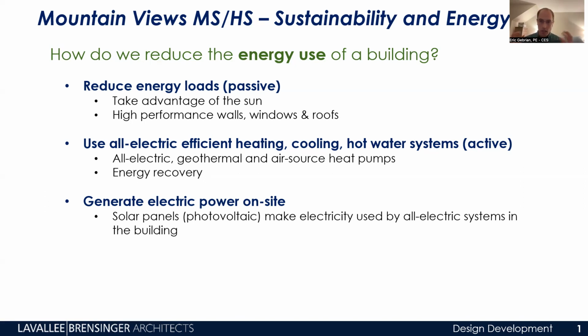We heat all that incoming air to 70 degrees in the wintertime—if we just exhausted it with no energy recovery, that would be a huge waste of energy, kind of like going right out the chimney. So we have energy recovery on our ventilation equipment that keeps about 70 to 80% of that energy back in the building. Those are the two major HVAC technologies we're using to really lower our energy use.